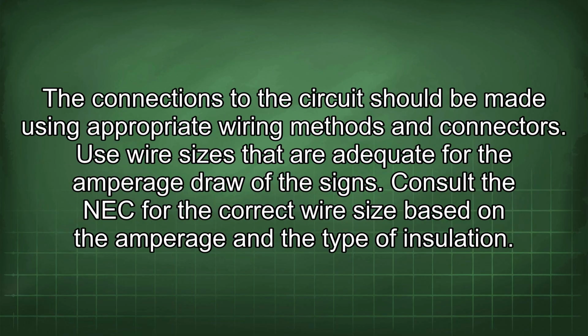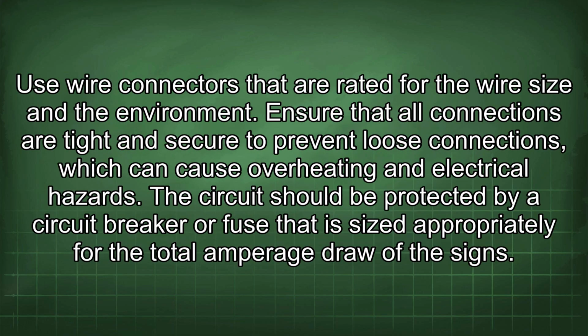The connections to the circuit should be made using appropriate wiring methods and connectors. Use wire sizes that are adequate for the amperage draw of the signs. Consult the NEC for the correct wire size based on the amperage and the type of insulation. Use wire connectors that are rated for the wire size and the environment. Ensure that all connections are tight and secure to prevent loose connections, which can cause overheating and electrical hazards.